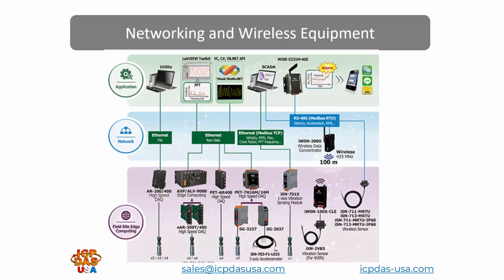We have networking and wireless equipment. You can see we have various switches. The NS205 for hardwired Ethernet, and then we have the IWSN200U wireless data concentrator, which can connect to the ISN 711 MRTU devices, and those can measure vibration, and that data can go to an Indusoft or Aveva SCADA system or a WISE 5231M 4GE wireless controller, which can handle if-then-else logic.